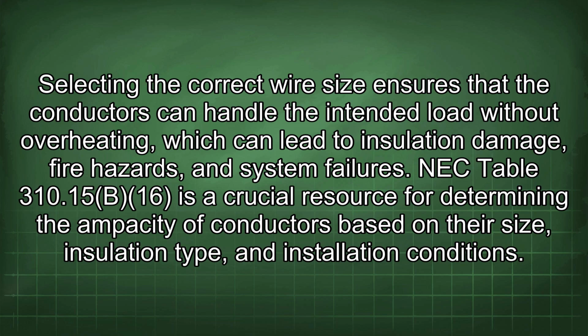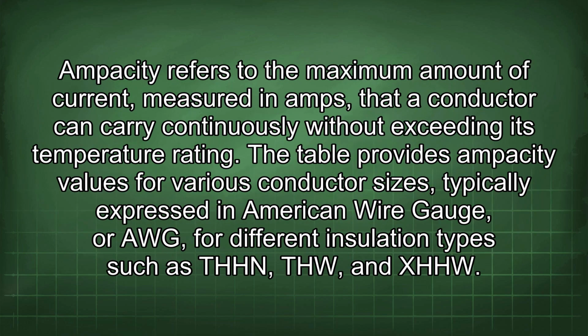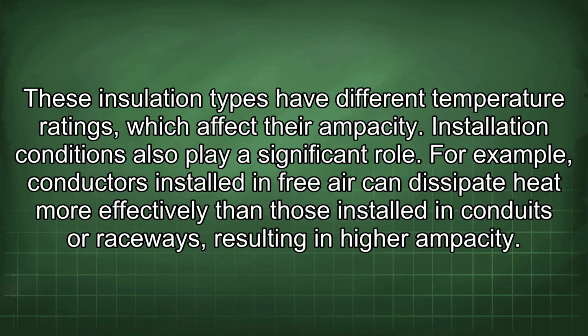NEC Table 310.15(B)(16) is a crucial resource for determining the ampacity of conductors based on their size, insulation type, and installation conditions. Ampacity refers to the maximum amount of current, measured in amps, that a conductor can carry continuously without exceeding its temperature rating. The table provides ampacity values for various conductor sizes, typically expressed in American wire gauge, or AWG, for different insulation types such as THHN, THW, and XHHW. These insulation types have different temperature ratings, which affect their ampacity.